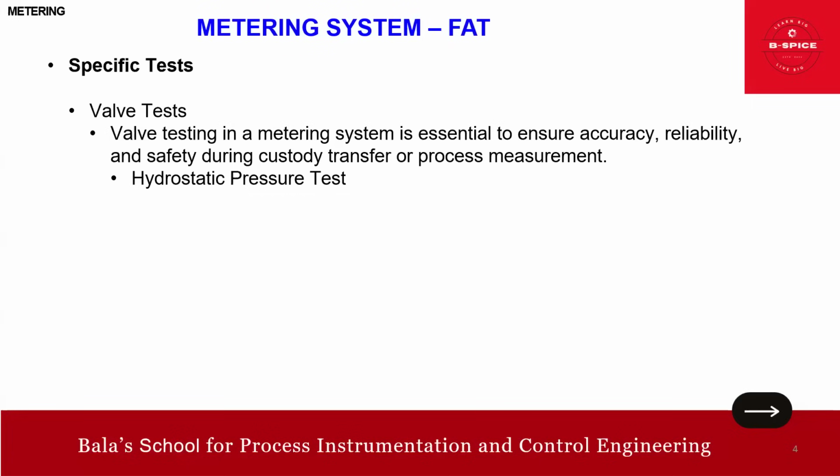So there are many tests, in fact. Let's go one by one. As usual, friends, we have to go for a hydrostatic pressure test. This is to verify the valve body integrity under pressure. For example, how do we do this? We apply a pressure, usually 1.5 times design pressure, using water or an inert fluid.